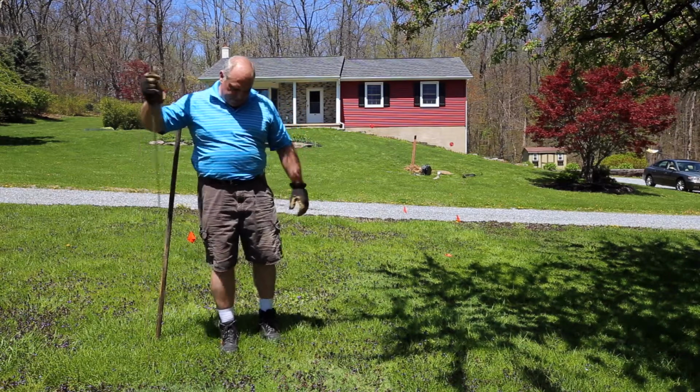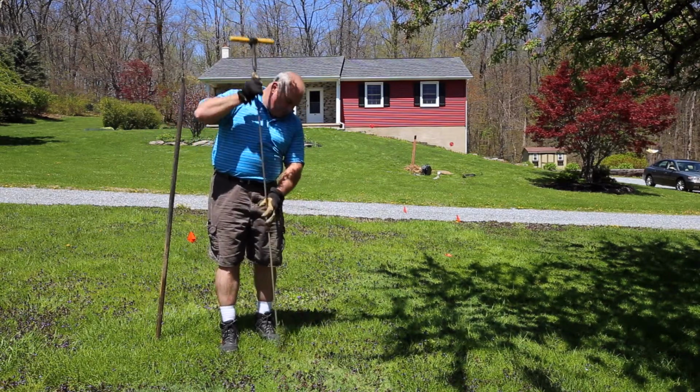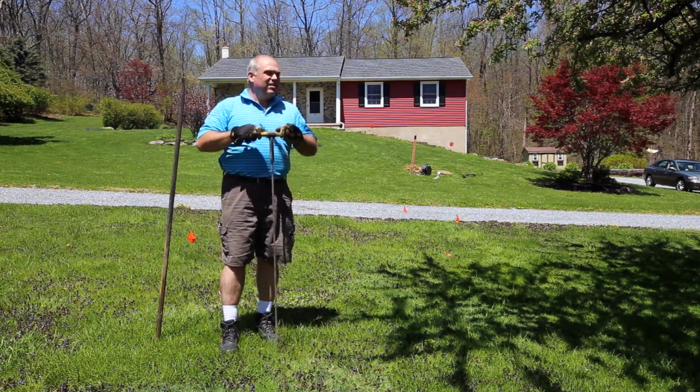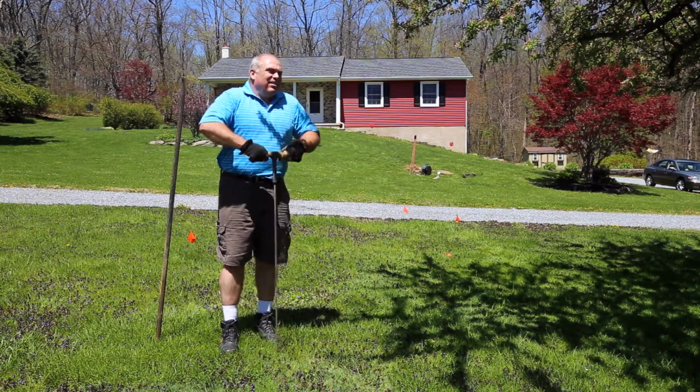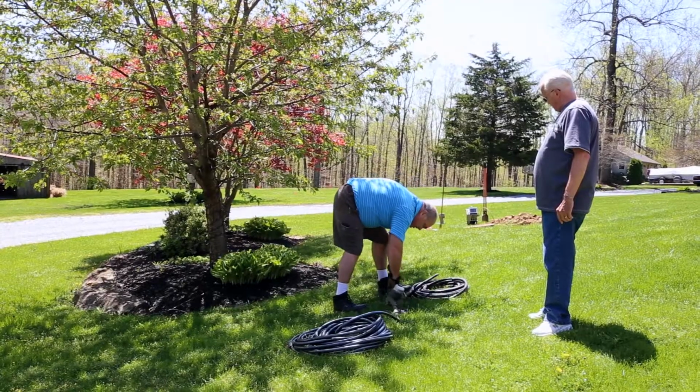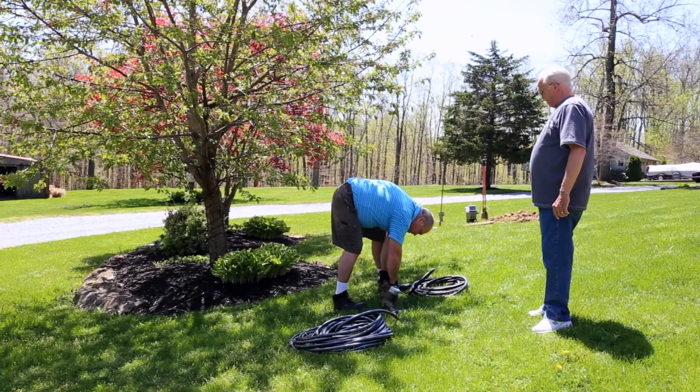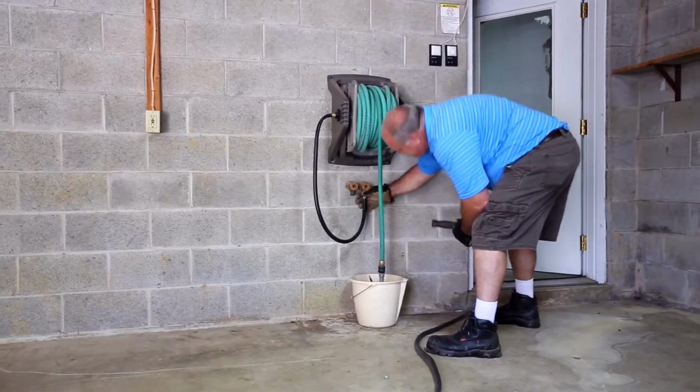Finally, we went on to locating the seepage bed, which is a gravel component on the other side of the drive, as I said, and it was dry because it's been vacant, and it may not have been getting full loading because of the leaking septic tank. So the combination of factors meant that we wanted to determine if that component could dissipate the design flow of a full potential house. We then started to administer the hydraulic load test flows.